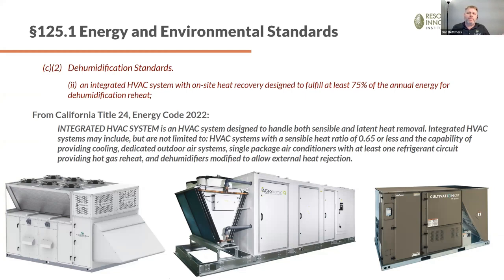Basically on par, either people use split systems with standalone dehumidifiers, or a lot of times these packaged units. Again though, check the efficiency - ask them how efficient is this going to be at my dehumidification. The other two units were made for dehumidification. This unit was kind of made for air conditioning with a little bit of dehumidification strapped on. So when you're looking at it, what's the efficiency? What's it going to cost me to operate this?